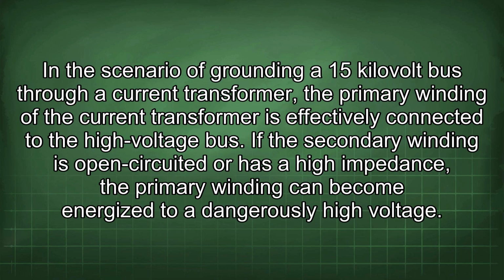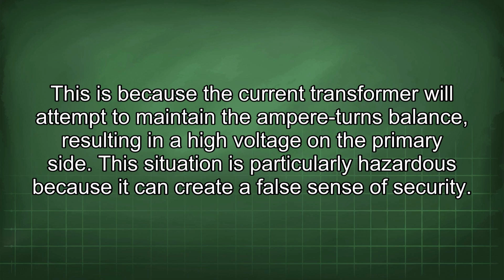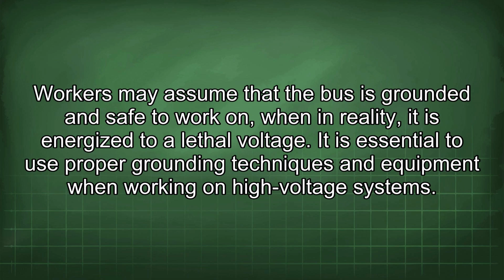In the scenario of grounding a 15 kilovolt bus through a current transformer, the primary winding of the current transformer is effectively connected to the high voltage bus. If the secondary winding is open-circuited or has a high impedance, the primary winding can become energized to a dangerously high voltage. This is because the current transformer will attempt to maintain the ampere-turns balance, resulting in a high voltage on the primary side. This situation is particularly hazardous because it can create a false sense of security. Workers may assume that the bus is grounded and safe to work on, when in reality, it is energized to a lethal voltage. It is essential to use proper grounding techniques and equipment when working on high-voltage systems.